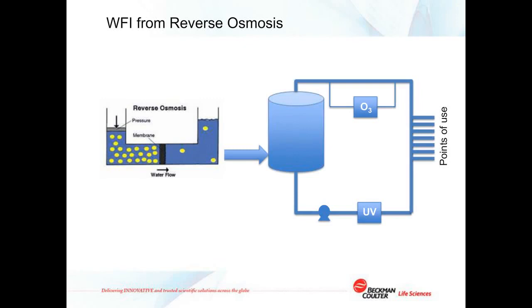So let's take a brief look at the alternative systems proposed for water for injection production using reverse osmosis and ozone. Under normal conditions, the osmotic pressure across a water-permeable membrane causes the water to pass through the membrane to the side with the highest concentration of salts. Reverse osmosis, as the name suggests, reverses the direction of the water flow by pressurizing the incoming water side of the membrane so that clean water is pushed through the membrane, leaving the contamination that was present on the water behind.